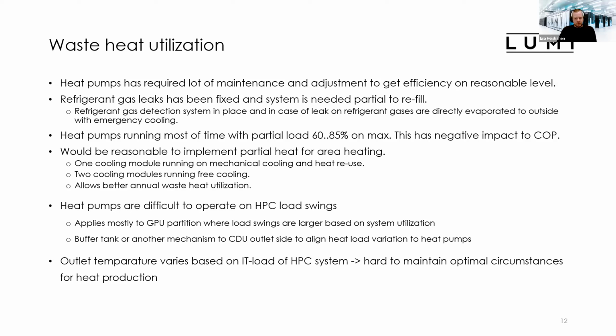So because this first phase installation was only less than 1 megawatt in total power, we had a single heat pump running at 50% or less of its power. And when the full system and GPU partition was installed and our heat production power started to rise over 2 megawatt per heat pump, we had to redo some adjustment.